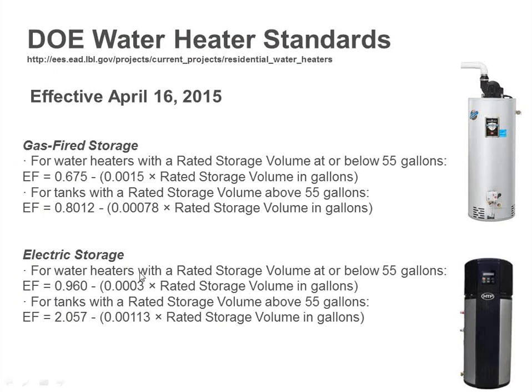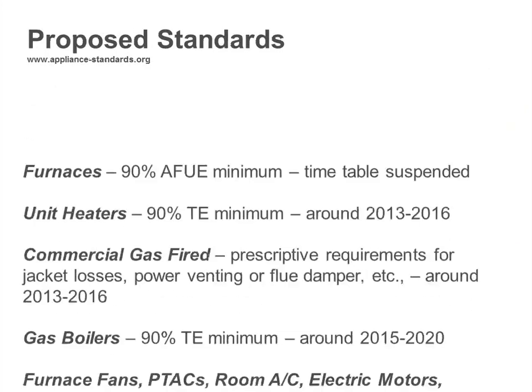Electric, similar thing. Below 55 gallons, the current technology is pretty much there already. But above 55 gallons, you have to have an energy factor of 2.057 as a minimum. As you probably know, an energy factor of approximately 1 is basically 100% efficient. So we're saying we have to be 200% efficient, which basically means you have to use heat pump technology, something where you're not burning a fuel to make heat. You're just using a fuel to move heat from one place to another. So expect that to come down the pipe in about a year and a half. You'll see big changes on the water heater side.